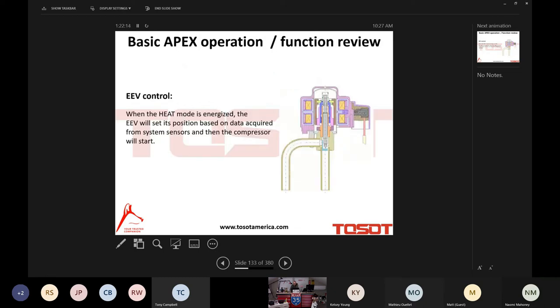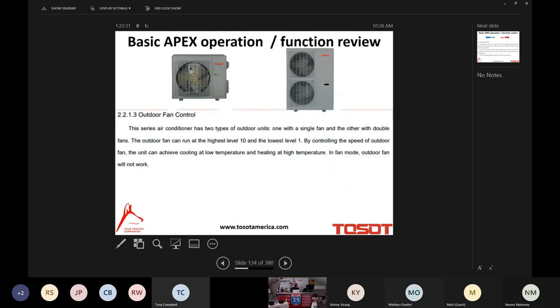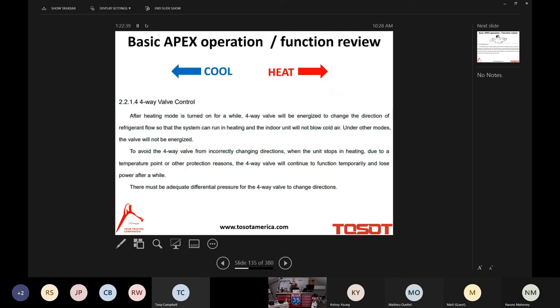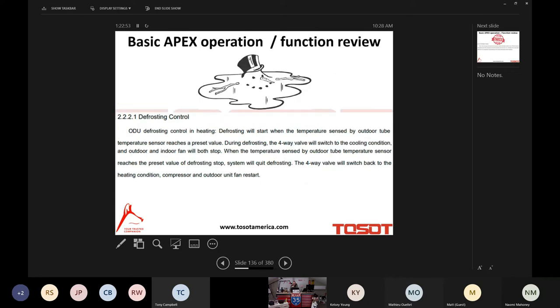Again, this is necessary for the inverter compressor to run without short cycling and to last a very, very long time. The EEV in the heating mode, I can actually operate this EEV. You can watch the pin metering the refrigerant going through the valve and the two EEVs of the outdoor unit being used only in the heating mode. The outdoor fan, whether it be one or two, is obviously controlled with 10 levels of speed for the outdoor fan motor. Cooling and heating, nothing extraordinary here, guys. Again, all done at the reversing valve so that the system can either manually or automatically go from heating to cool and vice versa.